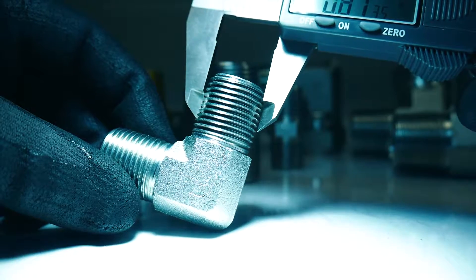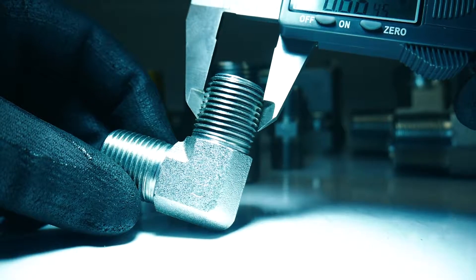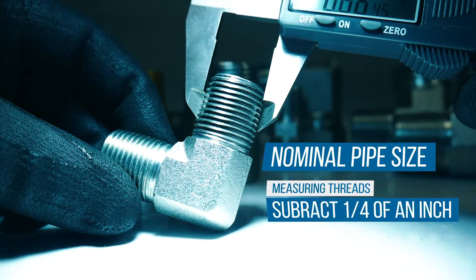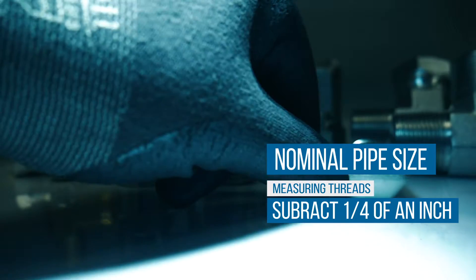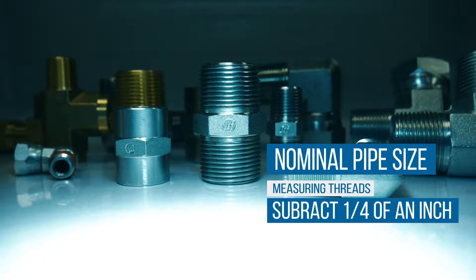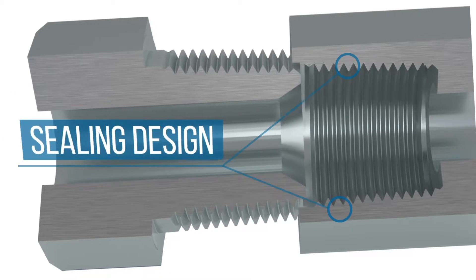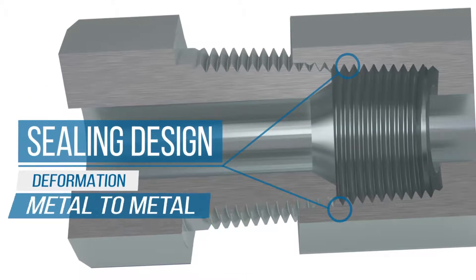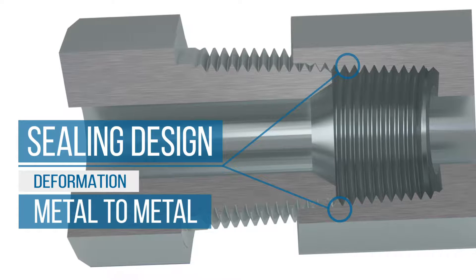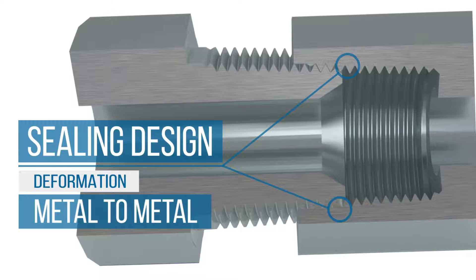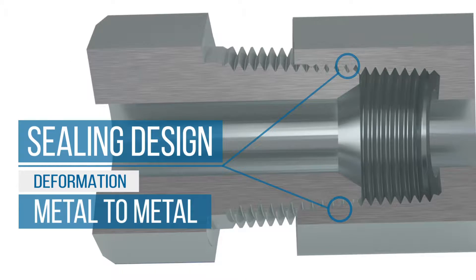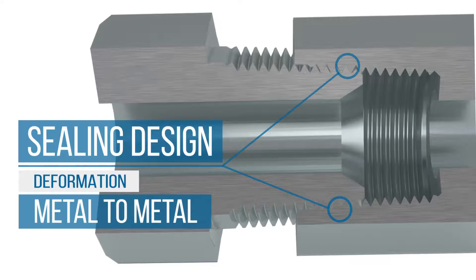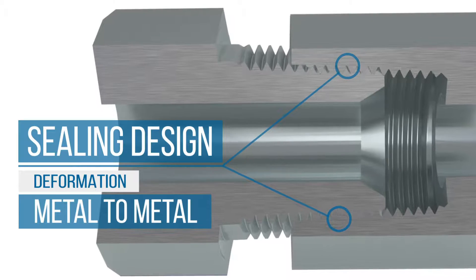The nominal pipe size can be identified by physically measuring the thread diameter then subtracting a quarter of an inch. NPT connections rely on thread deformation, a metal-to-metal sealing design where the threads of the connectors themselves form together.